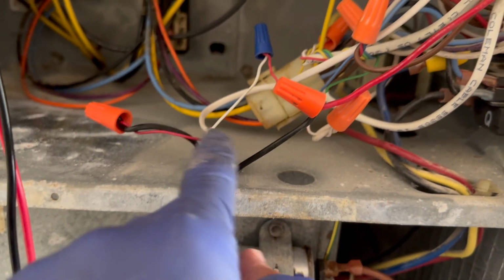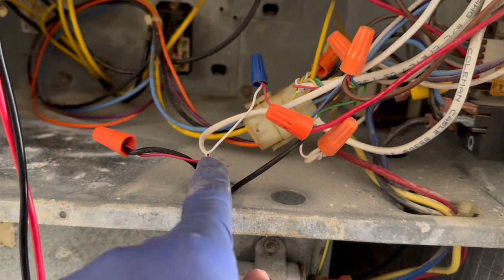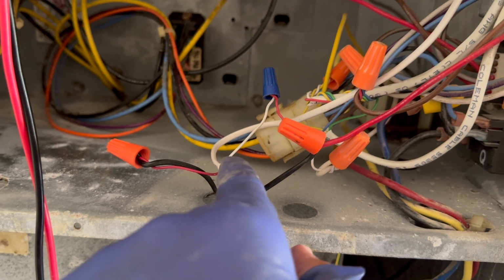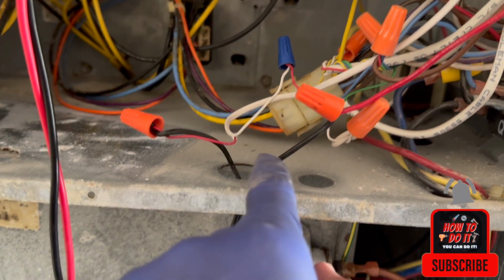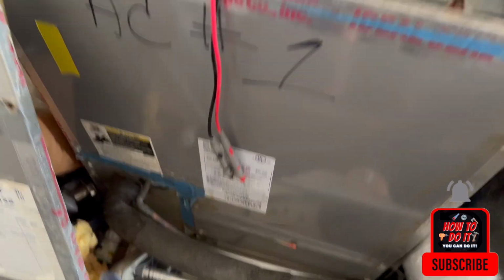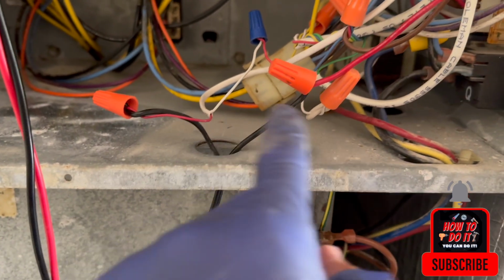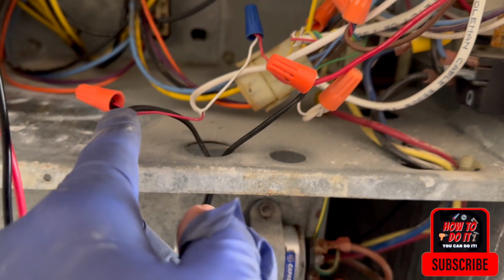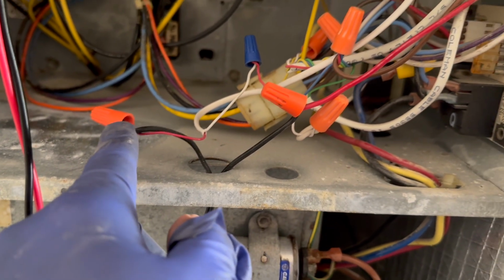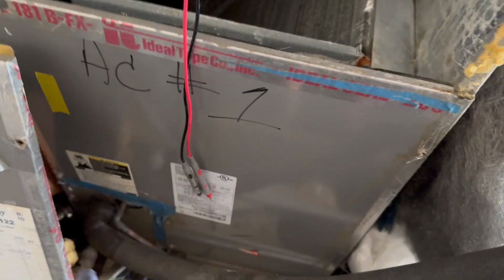Okay, so 25 volts is coming over here. Normally this wire is connected directly to this, and you have the 25 to 28 volt AC going to the thermostat, but there is a float switch in the middle, and this float switch goes over there. Seems like the float switch is disconnected because I do have power over here, but I don't have power here. That tells me the float switch is activated.